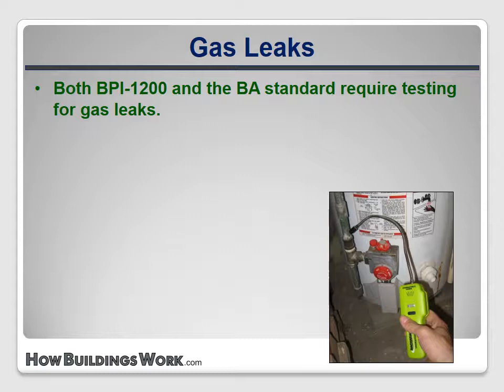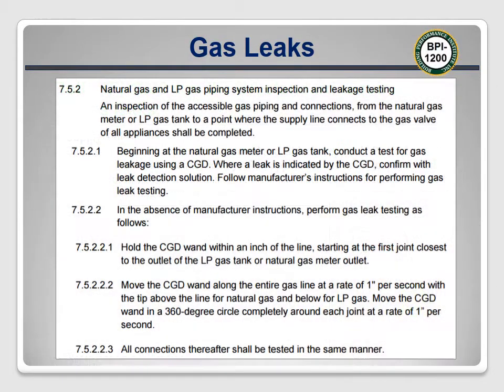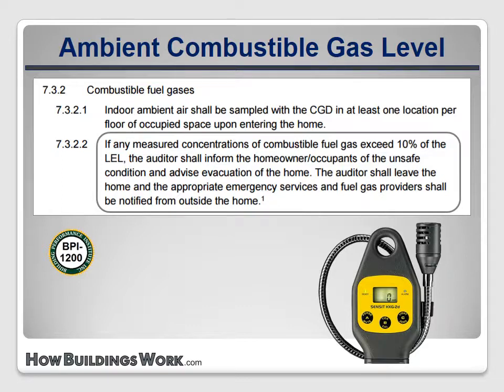Both BPI 1200 and the BA Standard require testing for gas leaks and verifying any leaks with a bubble solution, and both require that repairs to any leaks be included in the work scope. BPI 1200 adds a requirement to measure ambient gas level in the house to ensure gas leaks aren't creating an explosive condition. If the level exceeds 10% of the lower explosive limit, the auditor shall inform the occupants of the unsafe condition, advise evacuation, leave the home, and notify emergency services and fuel gas providers from outside the home.